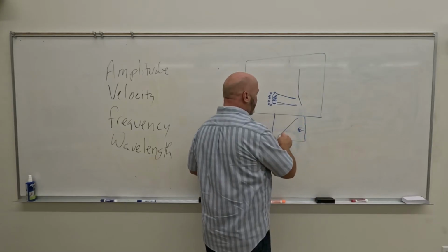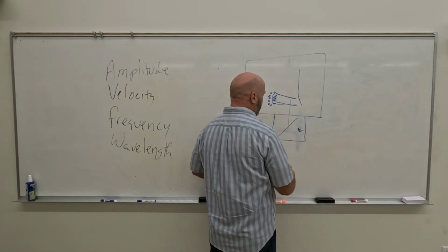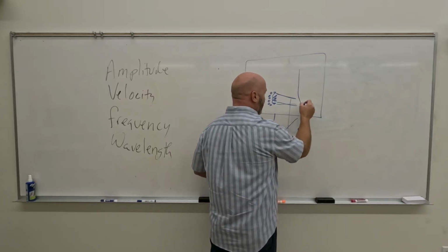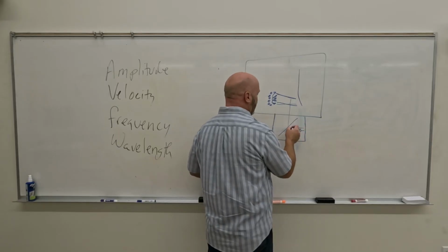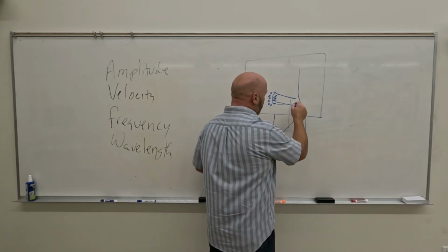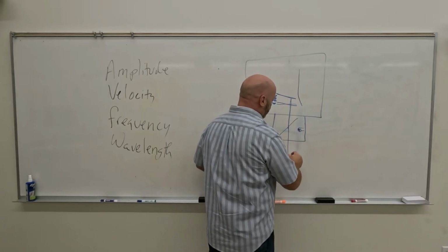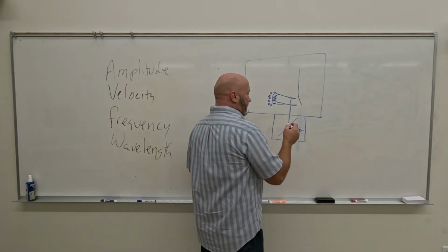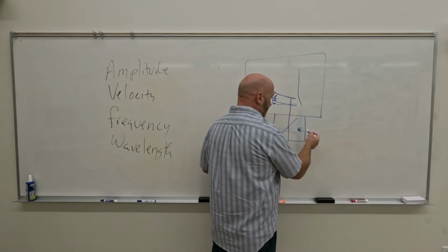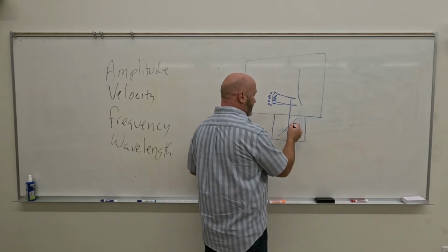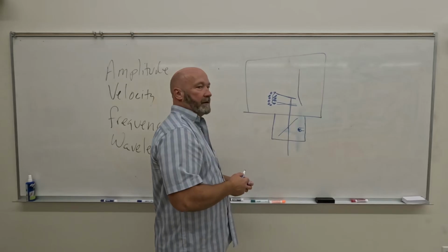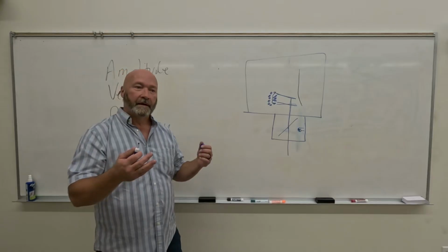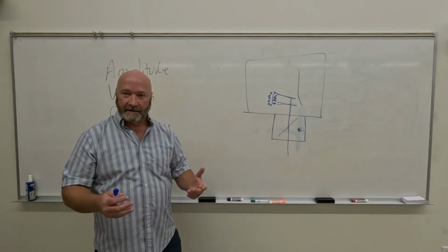What we have, though, is a mirror, so the x-ray photons actually pass through the mirror, and for reasons we'll talk about later in the semester, the distance between here and here has to be exactly the same as the distance between here and here, not drawn to scale, but the x-rays pass through that. So since we don't see x-rays, we have to have a way to see where the light field is going to be. So we have a light, right? Again, same kind of energy, electromagnetic energy, behaves a lot in the same way.